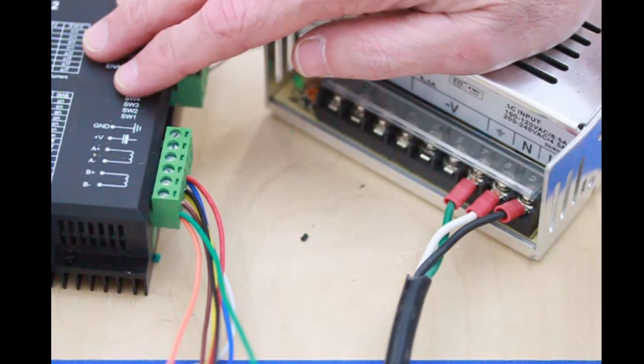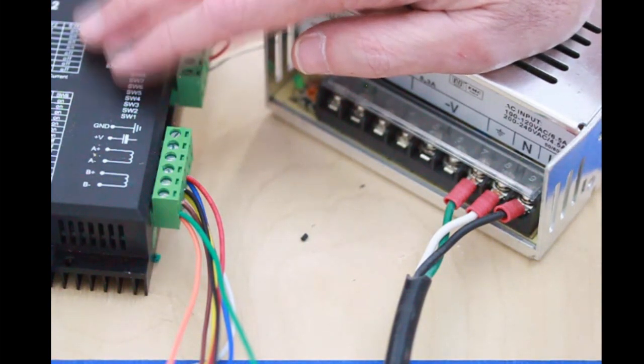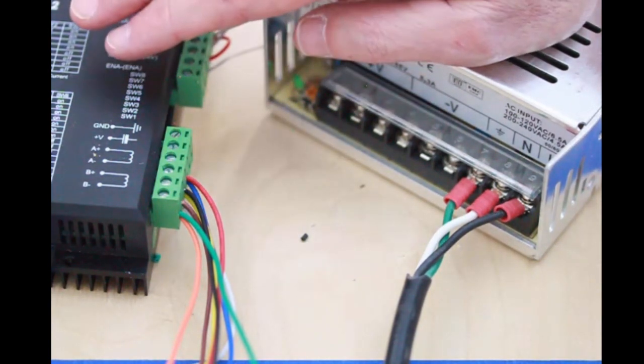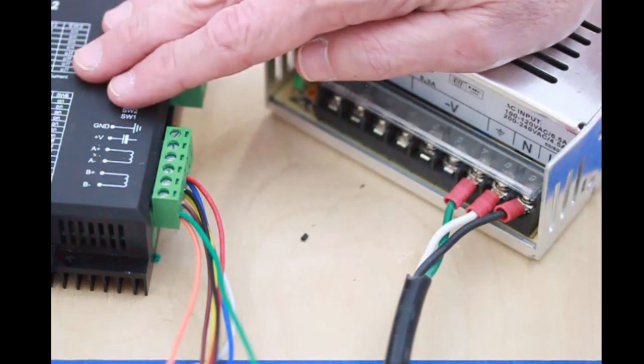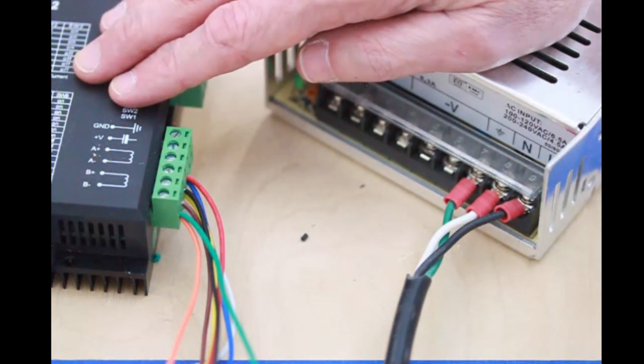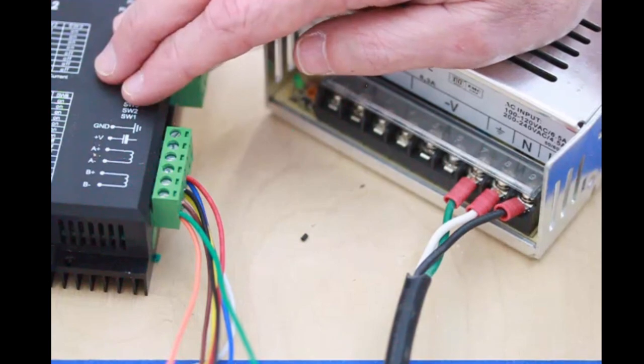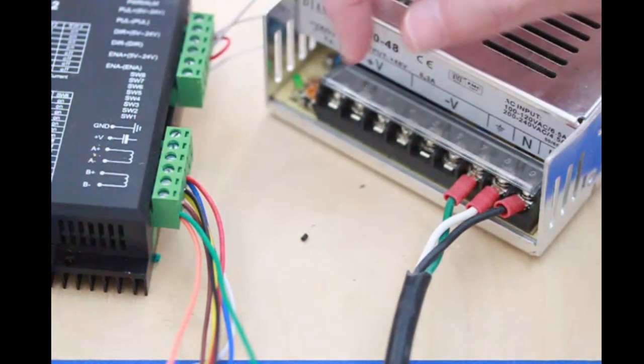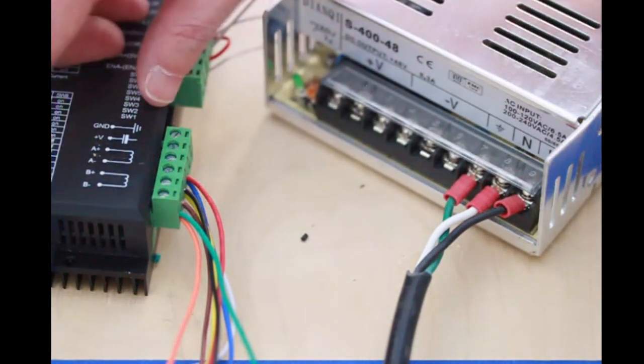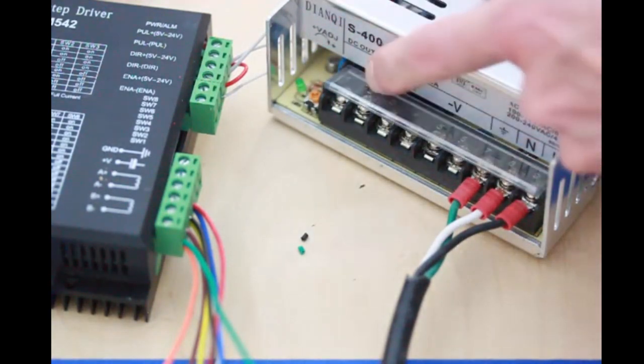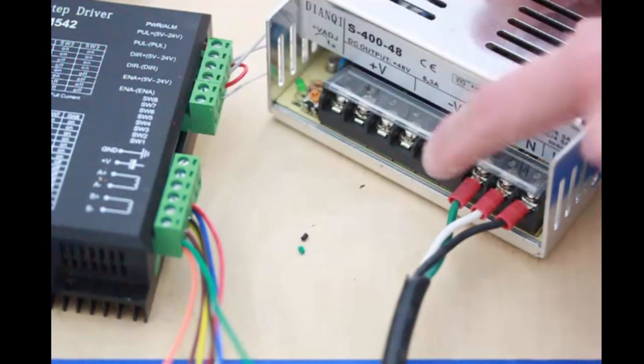In this case, I'm using a 48 volt power supply. Depending on the motor and driver configurations or specifications, you may be able to use a single power supply. You may also need to use multiple power supplies, or a single power supply with a higher voltage and current rating. Just like the other power supply in the previous video, the terminals are labeled V plus and V minus.